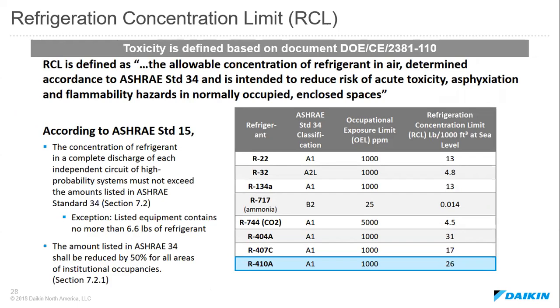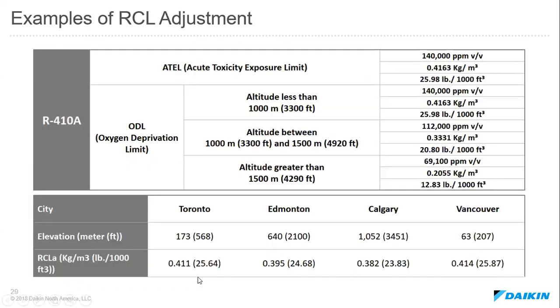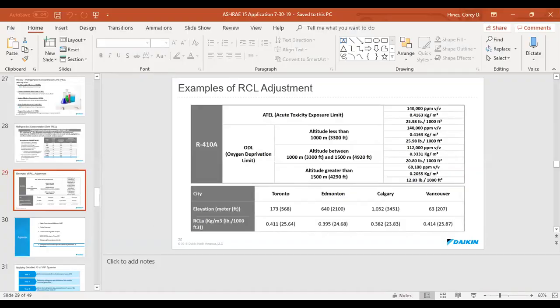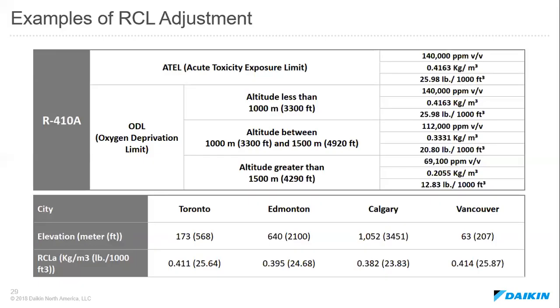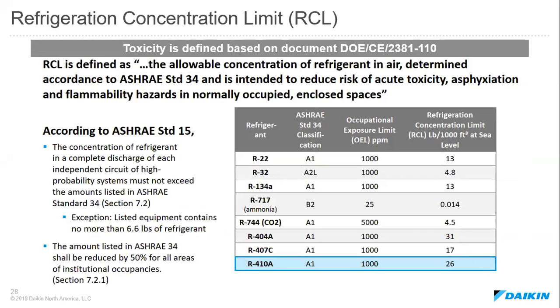So, the goal, like I said, is to reduce the risk of acute toxicity, asphyxiation, and flammability hazards in normally occupied or enclosed spaces. And so, as you look at the different charts for ASHRAE Standard 15, there are, for each refrigerant, like I mentioned earlier, a trade name and a classification that would put it into group A or B. It has an occupational exposure limit that's defined in parts per million, and then it also has a refrigerant concentration limit as well. And that refrigerant concentration limit testing is actually done at sea level.